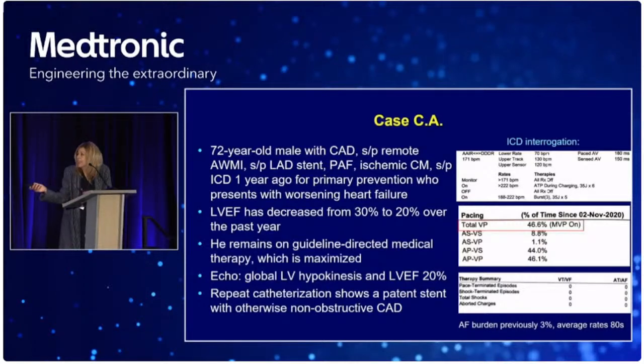But what we notice is, here's the programming, and it looks pretty decent. I don't know why they're at 70 beats a minute, but they're programming some reasonable therapies. Here it's a monitor zone and some therapies in here. But what you see here to highlight is you're now pacing about 47% of the time, and they're using MVP, so it's a Medtronic device, and that's managed ventricular pacing to minimize ventricular pacing. So you won't conduct, you'll drop a beat, you'll conduct as long as you can, and then you'll drop a beat, and then the device will pace because it sees a dropped beat. So basically you're already doing that.